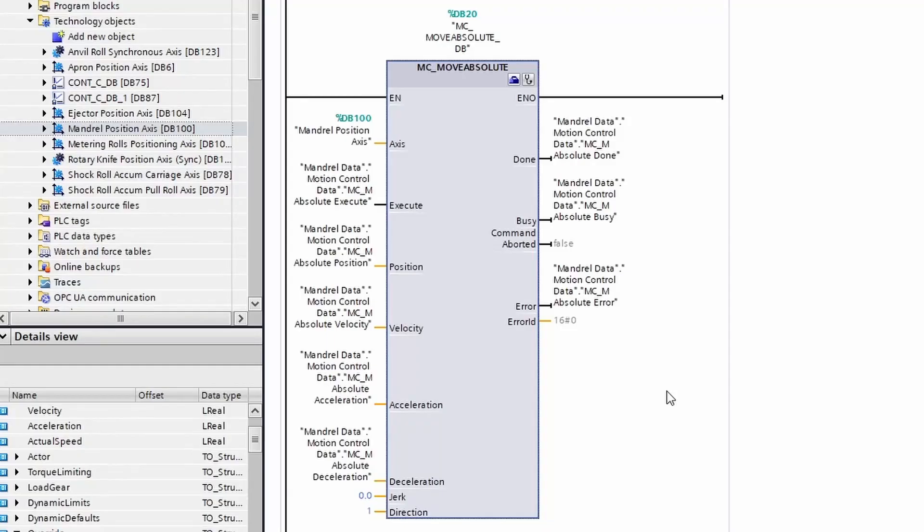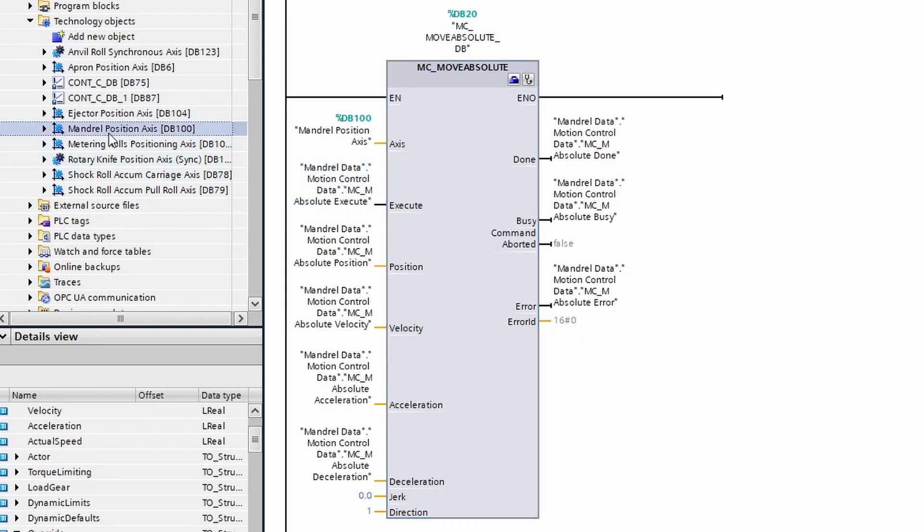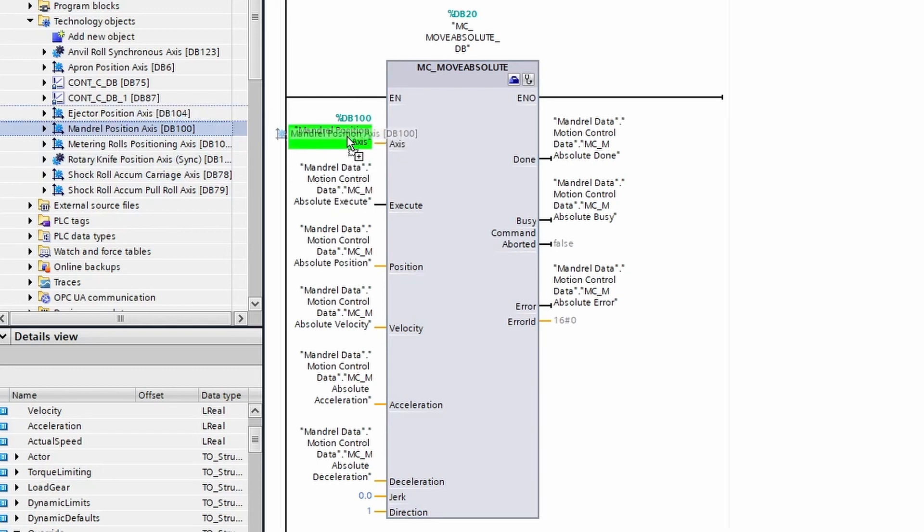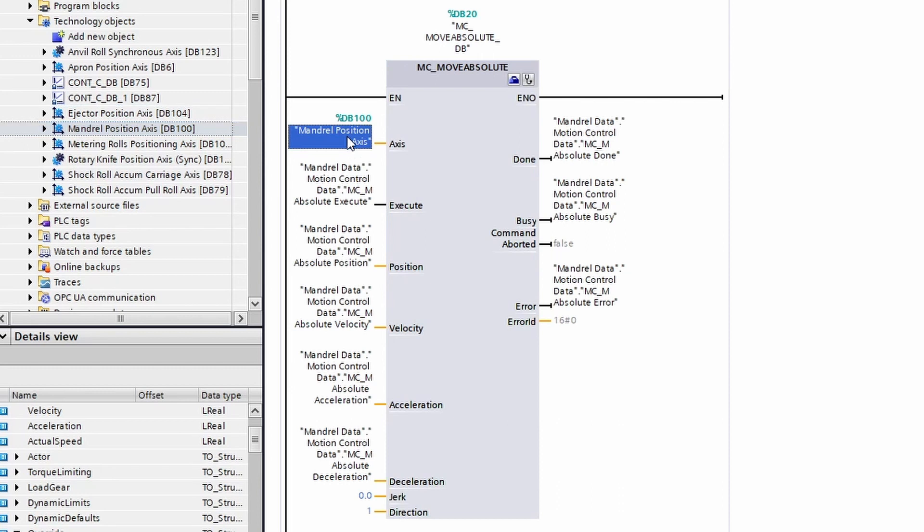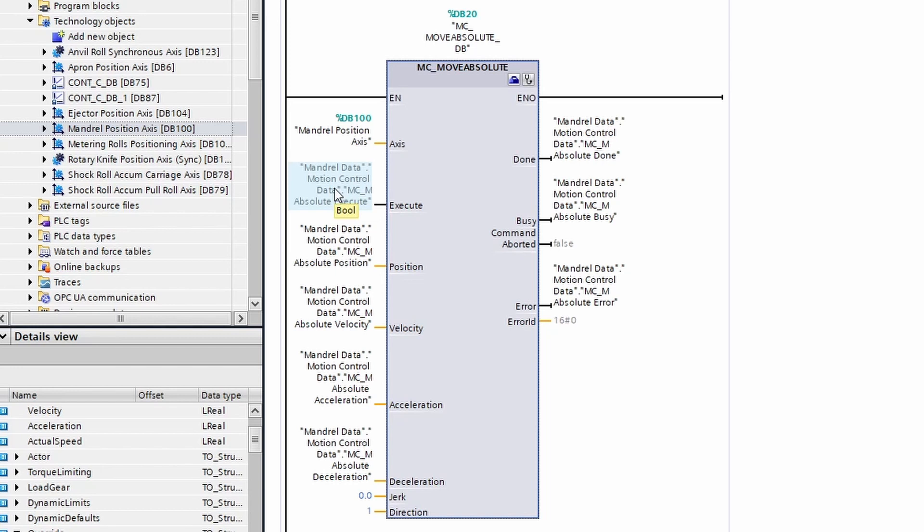Now let's talk about the inputs of the MC_MoveAbsolute. As always, the axis input can be linked with our technology object directly from the project tree by dragging the object into the axis parameter. The execute, as with all motion functions, is a positive edge triggered input.